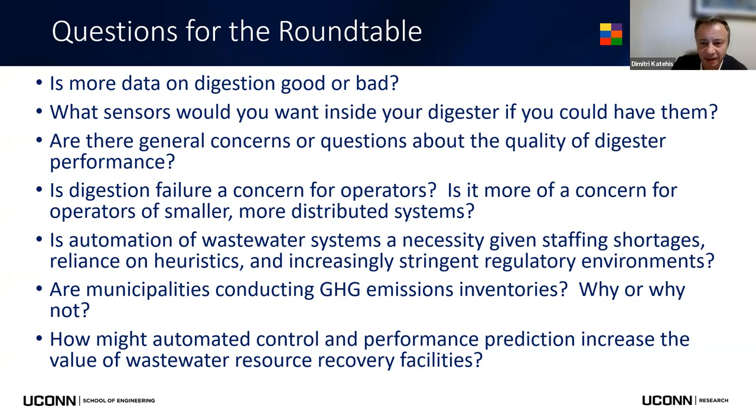Well, remember that the saving grace in digesters is that you have multiple days of solids retention time. Hopefully more than 15. And ideally, when we're heavily loading digesters in particular, we're targeting something on the order of about 25 days. Ideally, the combination of pH and alkalinity is what you're targeting, but if you don't have alkalinity, pH is an indicator.